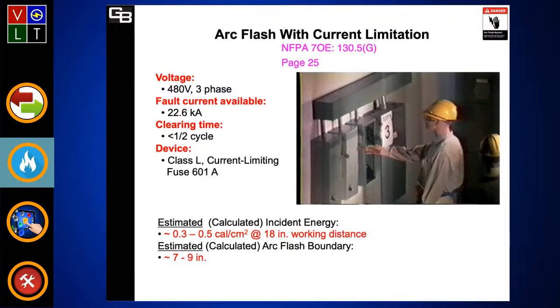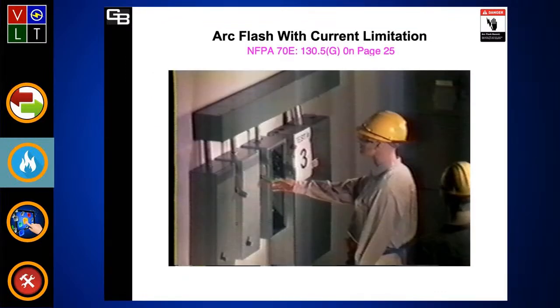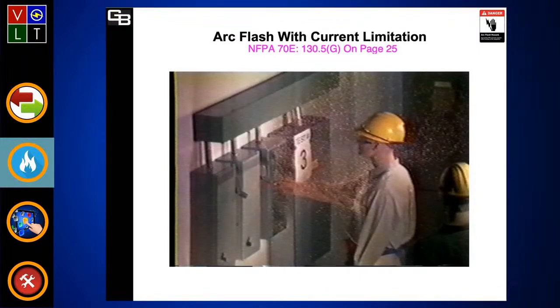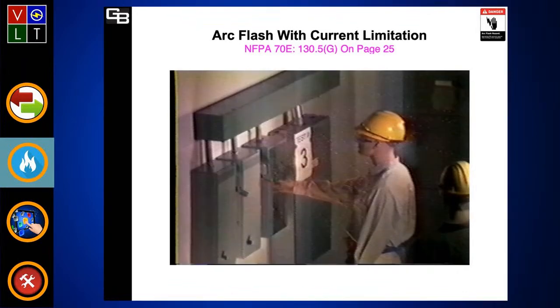Go ahead, James, go to the next. Now here's the ignition, and the next one will show you when the electrical arc develops, and you can see the amount of energy that's released. If you visualize a peak current going straight up in a waveform, up to the peak, down at the very bottom you'll have a little red area that's a half cycle clearing time. That's what we're looking at here. We're clearing in a half cycle the protective device supplying this area. Now see how it's reduced?